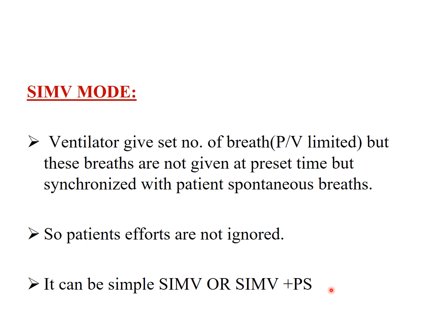So we talked about the trigger: the time trigger, the pressure trigger, and the flow trigger. The second thing is, once the breath is triggered, how long the breath is going to go in, how long the inspiratory phase is going to last. This is limited either by the pressure or the volume. So how long it is going to last is cycling, and how much breath is going to be delivered is limited by either the pressure or the volume. So we have got two types of ventilation: pressure limited ventilation and volume limited ventilation.